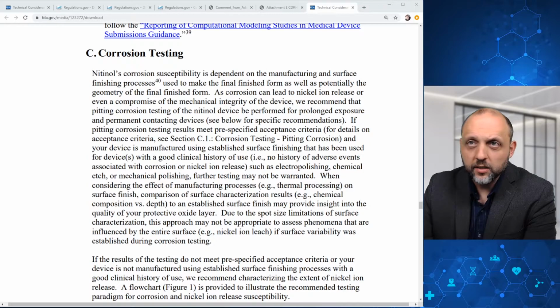In terms of corrosion testing, nitinol's corrosion susceptibility is dependent on the manufacturing and surface finishing processes used to make the final finished form, as well as potentially the geometry of the final finished form. As corrosion can lead to nickel ion release or even compromise of the mechanical integrity of the device, FDA recommends that pitting corrosion testing of the nitinol device be performed for prolonged exposure and permanent contacting devices. And there are some recommendations below. If pitting corrosion testing results meet pre-specified acceptance criteria, and the device is manufactured using established surface finishing that has been used for devices with a good clinical history of use, such as electropolishing, chemical etch, or mechanical polishing, further testing may not be warranted.